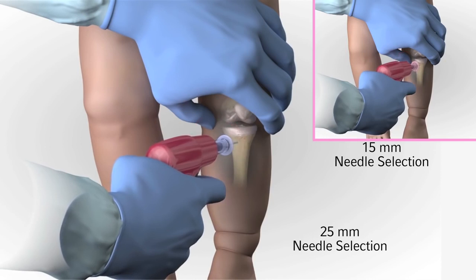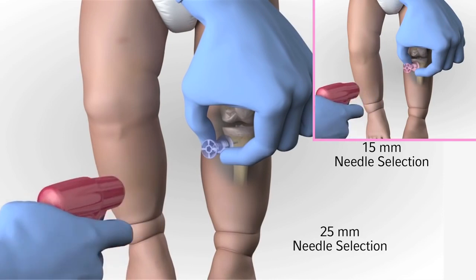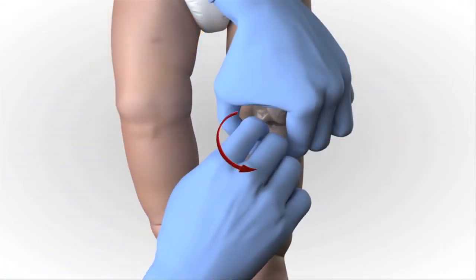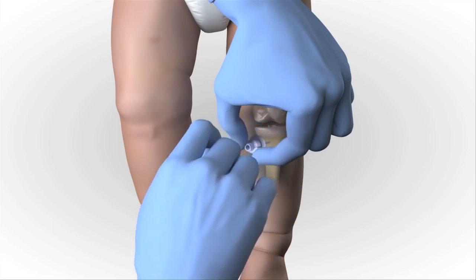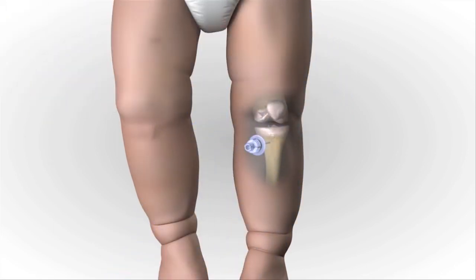Gently drill. Immediately release the trigger when you feel the pop or give as the needle set enters the medullary space. Avoid recoil. Do not pull back on the driver when releasing the trigger. Hold the hub in place and pull the driver straight off. Continue to hold the hub while twisting the stylet off with counter-clockwise rotations. The catheter should feel firmly seated in the bone.